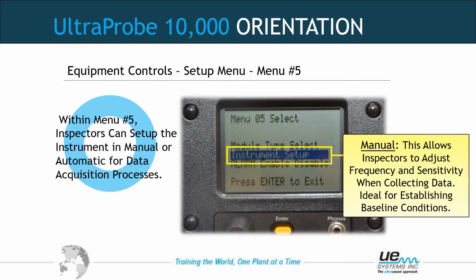If we were in automatic and we were to baseline a route and we come to our first record number 1, we set the sensitivity to 25. We set the frequency to 30. We store the information. It advances us to record number 2. Because it's in automatic, it is looking for a frequency and sensitivity to set it to for record number 2. It can't find anything because this is the baseline route, so it defaults to 40 kilohertz for the frequency and a sensitivity setting of 70. And this will do this every time you advance to the next record, making it very difficult when you're baselining. So while baselining, we would want it in manual, not automatic.